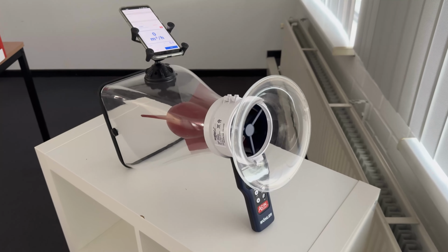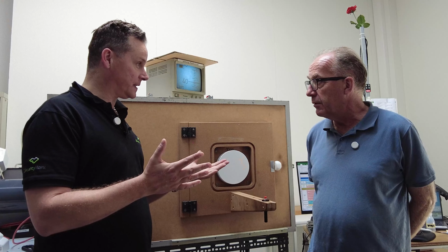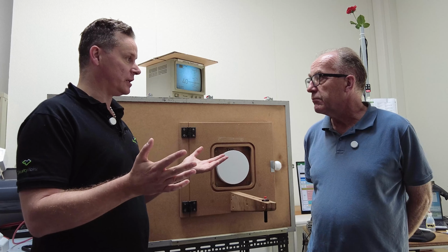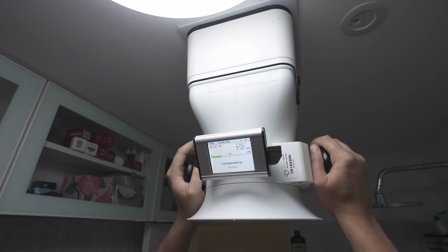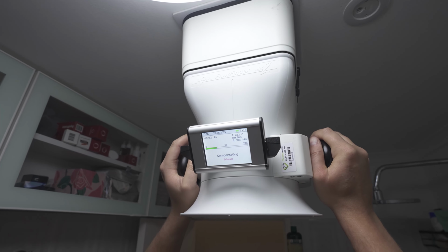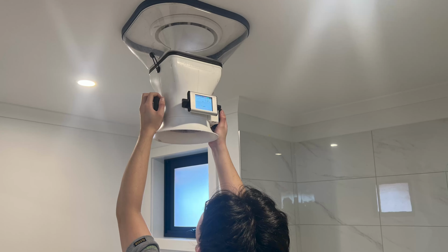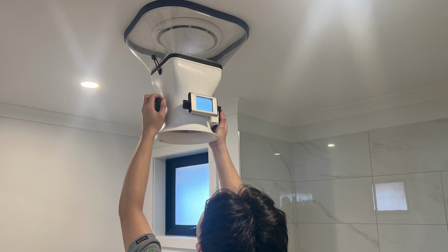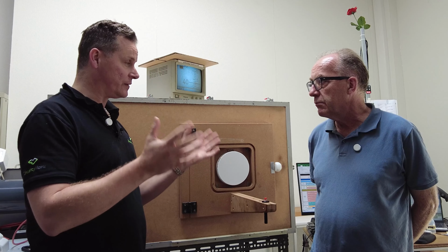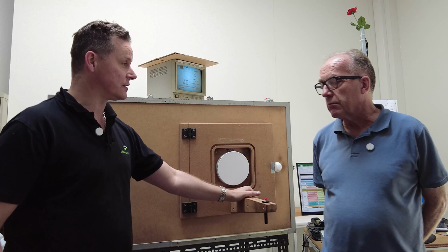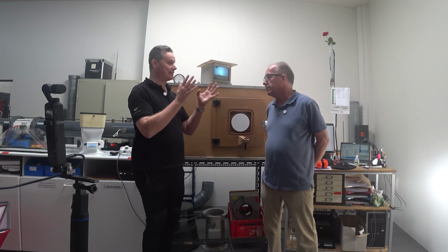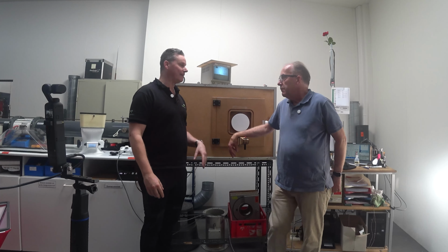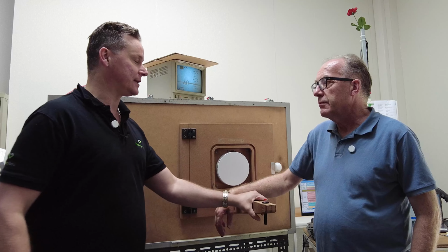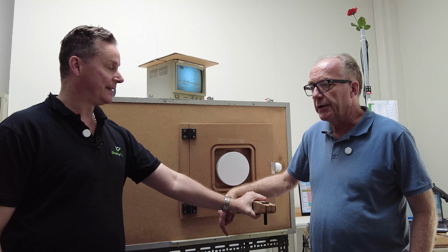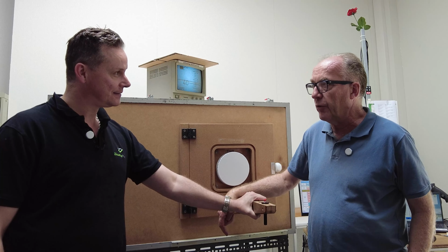Now, one thing that I've noticed from flow hoods that I've seen, and usually they come out for commissioning duct systems and plenums and just airflows coming out of things, is that they're always sort of restricted for the flow that you're trying to collect. They always come down to a sort of narrow spot where the airflows are actually captured. And I can see how that can potentially have an effect on the accuracy of the flow. Oh yeah, that certainly is a thing with flow hoods.